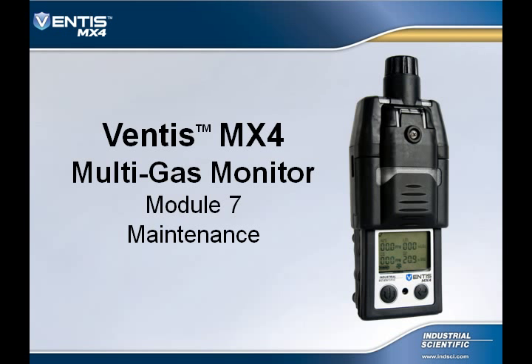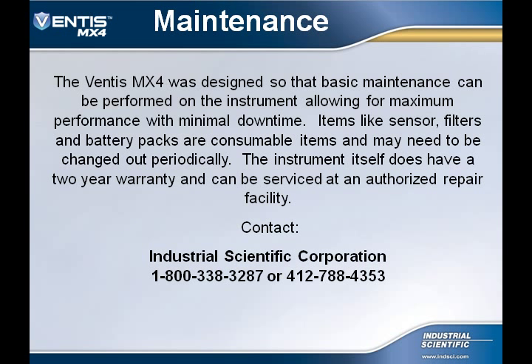In this module, we will be discussing the maintenance that can be performed on the instrument. The Ventis MX4 was designed so that basic maintenance can be performed on the instrument, allowing for maximum performance with minimal downtime. Items like sensors, filters, and battery packs are consumable items. Therefore, they need to be changed out periodically. The instrument itself has a 2-year warranty and can be serviced at an authorized repair facility.